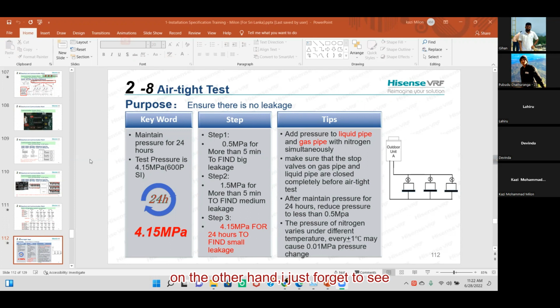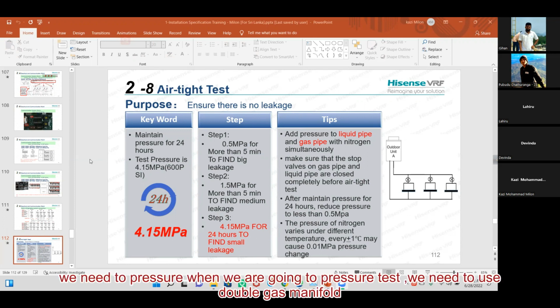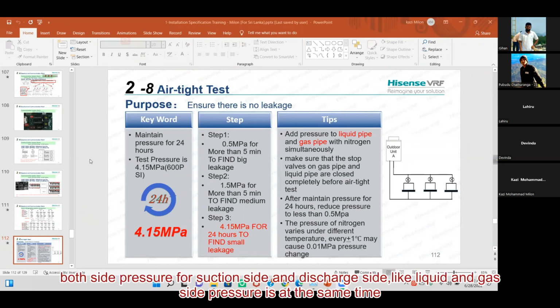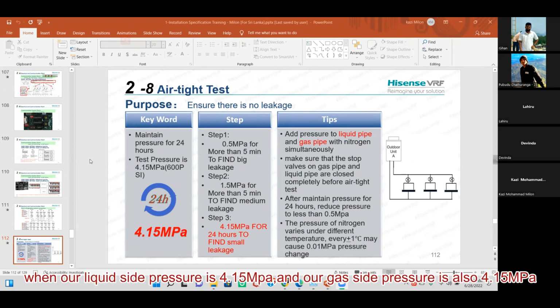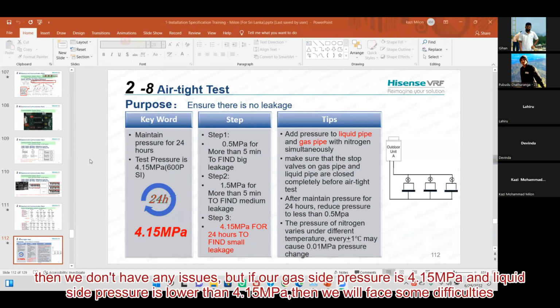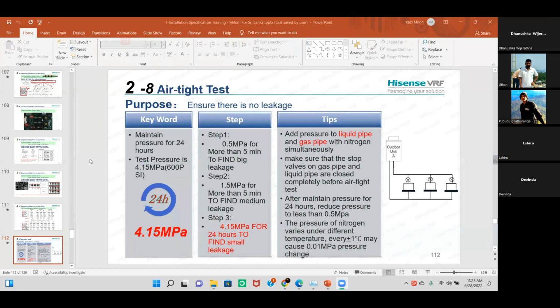On the other hand, I forgot to say, when we go for the pressure test, we need to use a double gauge manifold, for both sides, suction side and discharge side, like liquid and gas side pressure at the same time. When our liquid side pressure is 4.15 megapascal and our gas side pressure is also 4.15 megapascal, then we don't have any issues. But if our gas side pressure is 4.15 megapascal and liquid side pressure is lower than 4.15 megapascal, then we can face some difficulties, like our indoor unit EXV may not start. So we need to maintain both side pressures equal.